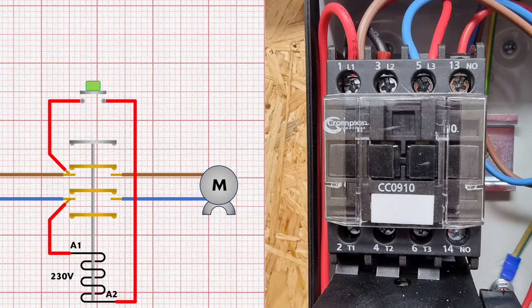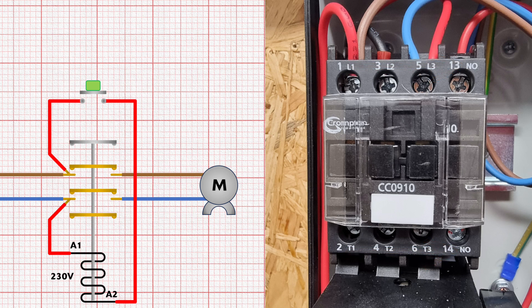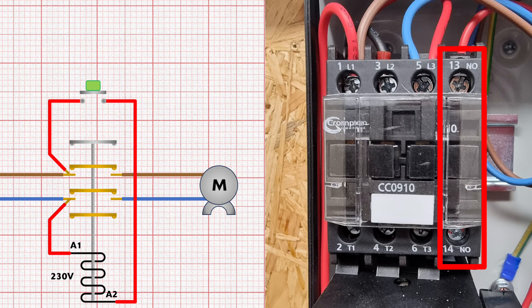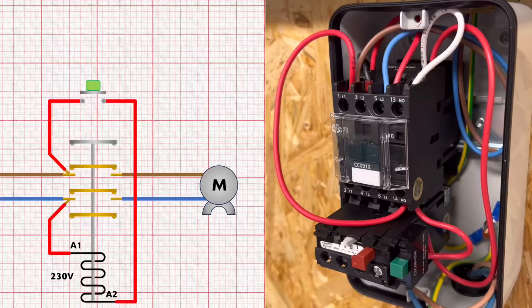If we look at the contactor, you may have noticed it has an extra pair of terminals for an additional contact. This is not designed to make and break the same level of current as the main contacts, but it can break smaller currents. It will make and break at the same time as the main contacts, and in this case this additional contact is normally open — meaning it's not making an electrical connection until the contactor is energised. The main contacts are labelled 1 to 6 with L1, L2 and L3 on the incoming side and T1, T2 and T3 on the outgoing side. The additional contact is labelled differently with a 13 and a 14, as well as the identifying mark of NO for normally open. This is what's referred to as an auxiliary contact, and most contactors will allow you to add extra ones which can be used for monitoring, signalling, and all sorts of other clever things.